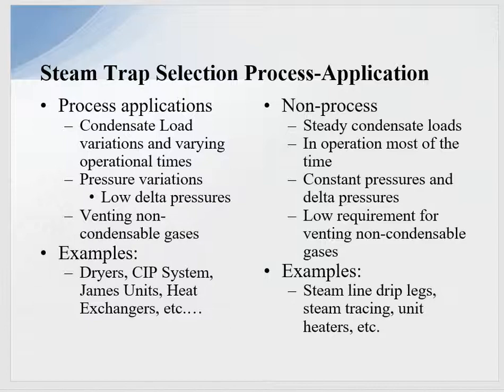Times vary when the process is in operation. Pressure variations: we can go down to low delta pressures because the steam valve controlling the process is going to modulate down, or it can be very high. The other thing on process applications — we want to be able to vent non-condensable gases to help get rid of gases so we get fast startup time.